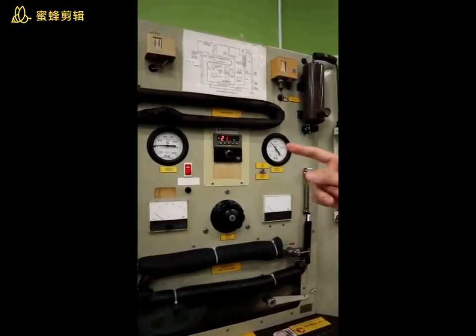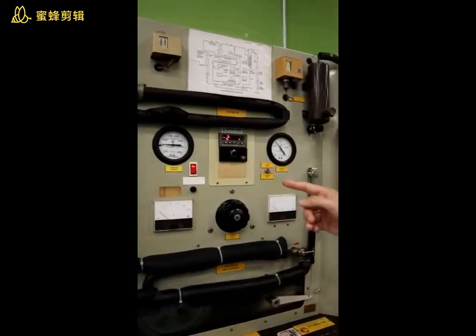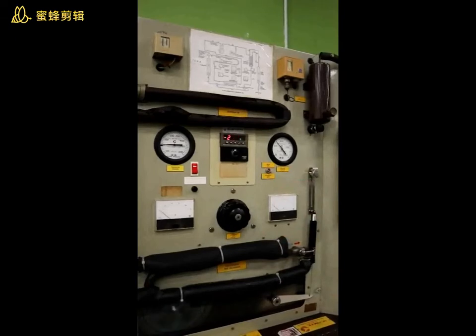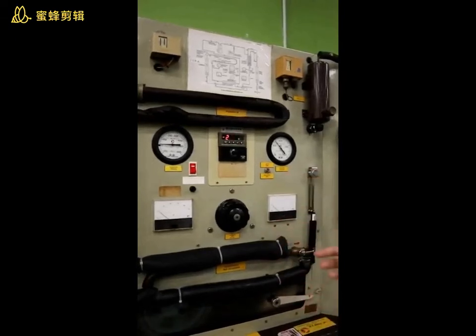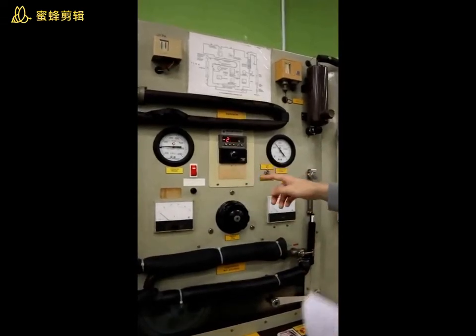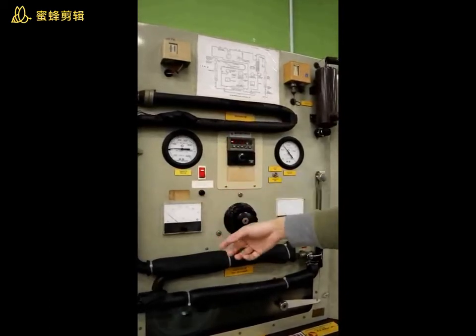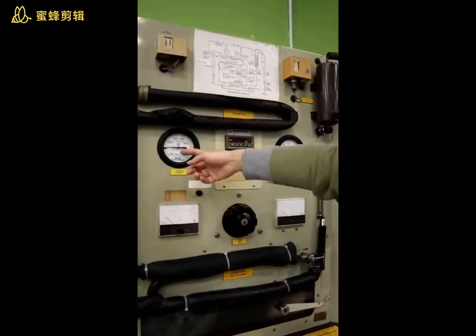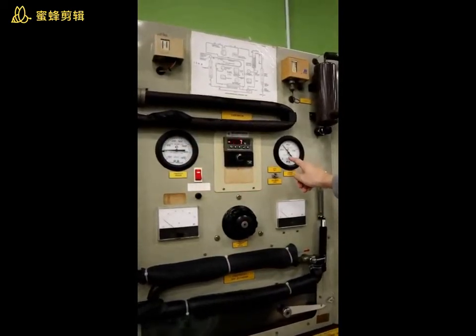Because there is only one thing that needs to be investigated, that is the degree of superheat, during the whole experiment we're going to maintain the other parameters at constant values, like the condenser pressure, because the evaporation pressure is correlated with the degree of superheat. When superheat changes, this changes, so we need to maintain it at a constant value.